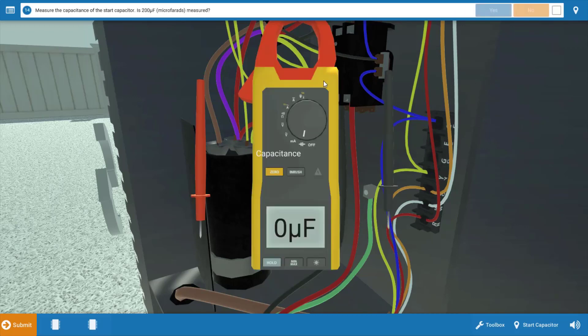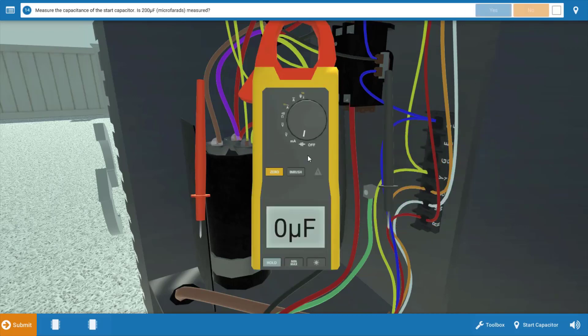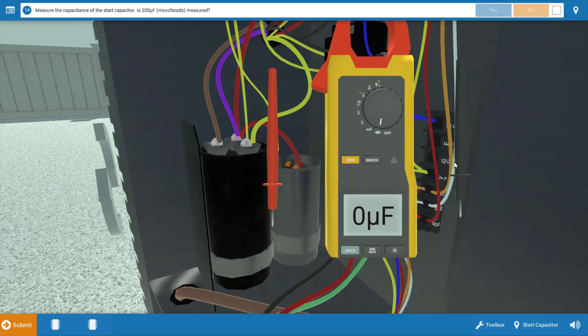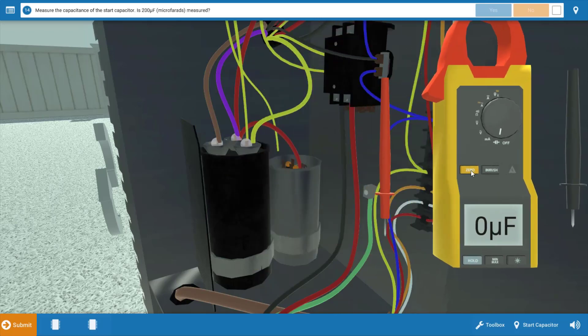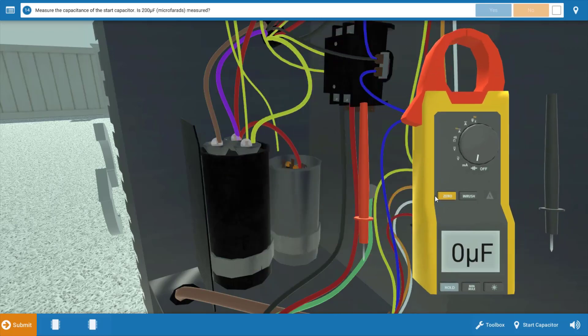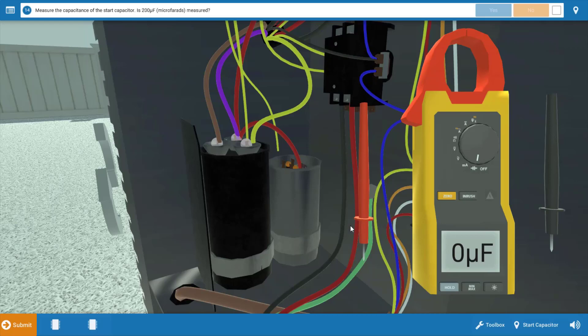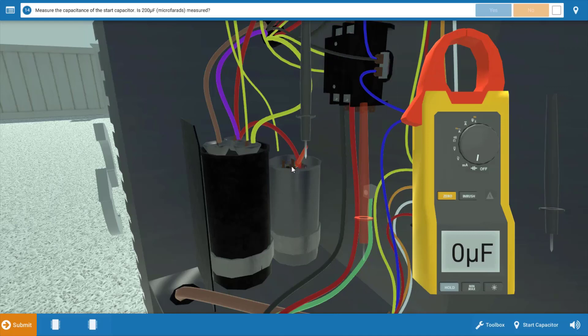And we're going to start by measuring the microfarad value of the start capacitor. Now, the start capacitor should measure 200 microfarads with this particular capacitor. You can look right on the side of the capacitor. There's typically a label on there that will give you the proper value of that capacitor as well as the voltage value. So we're going to place our leads across the two terminals on that capacitor and see if we've got 200 microfarads. And when we do this, we have zero, which indicates we have a faulty start capacitor here, and it's going to need to be replaced.